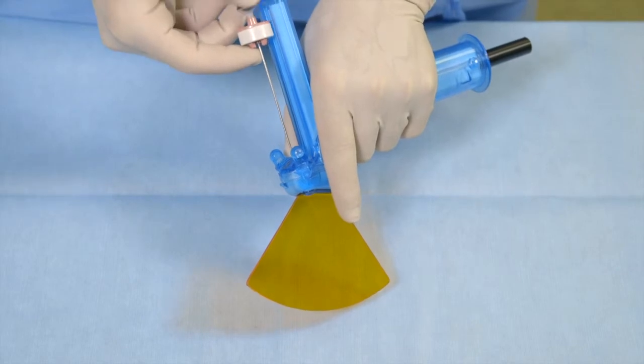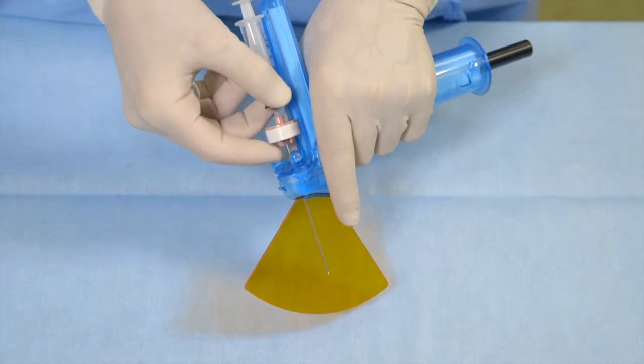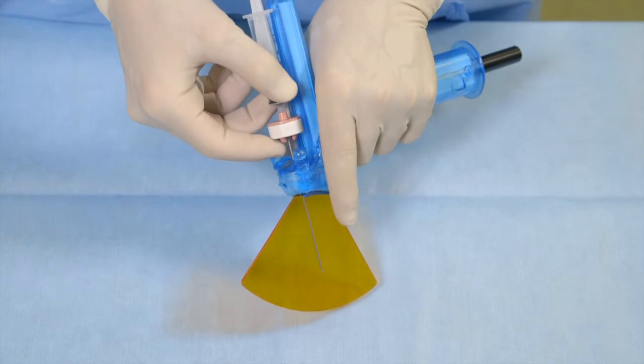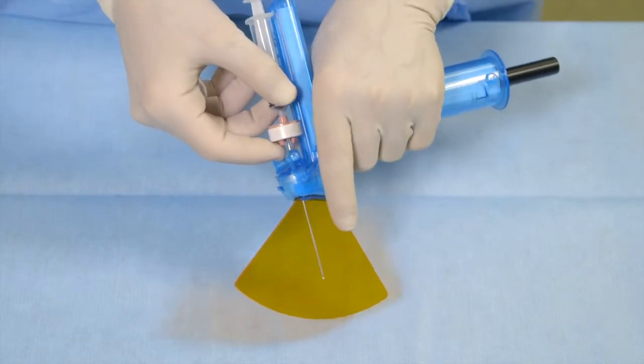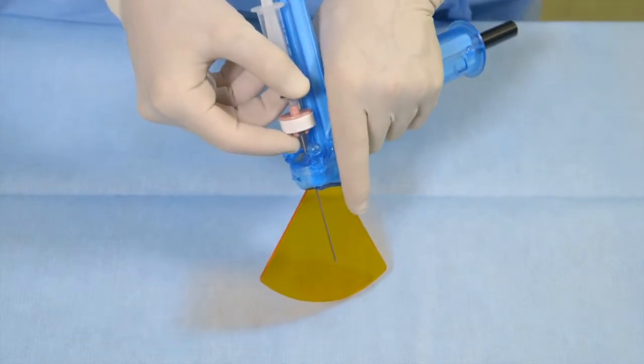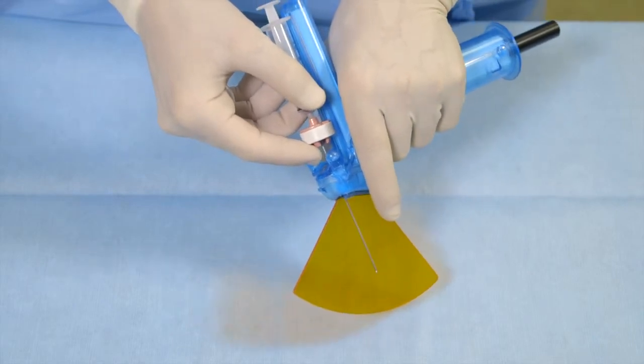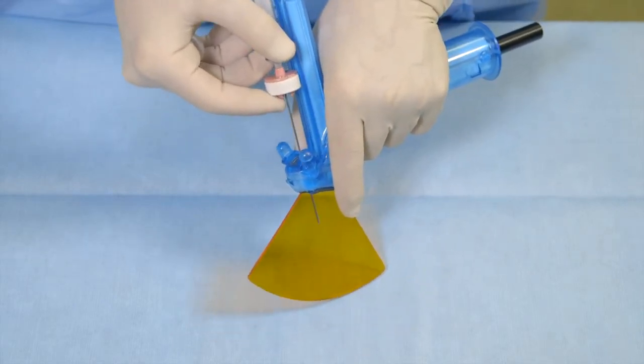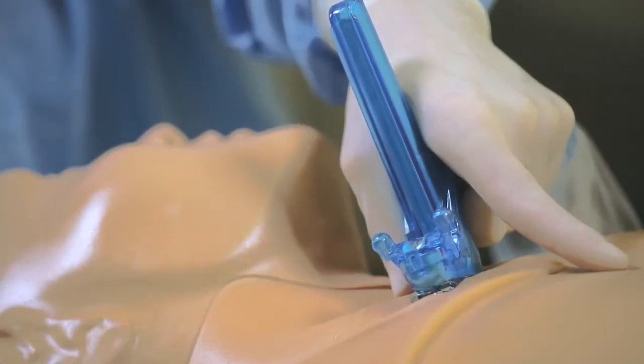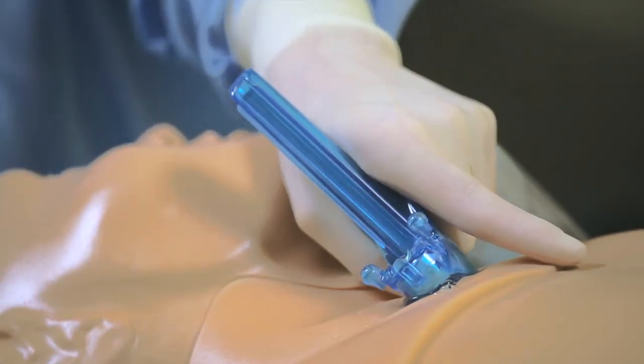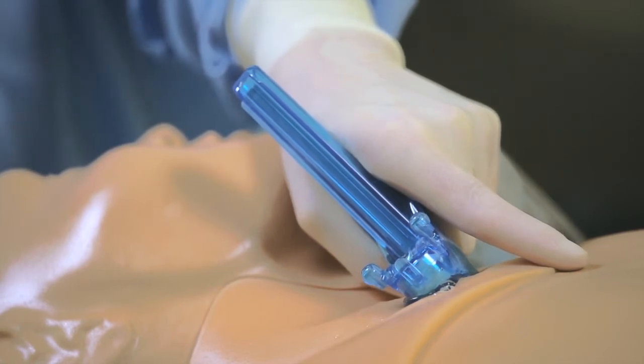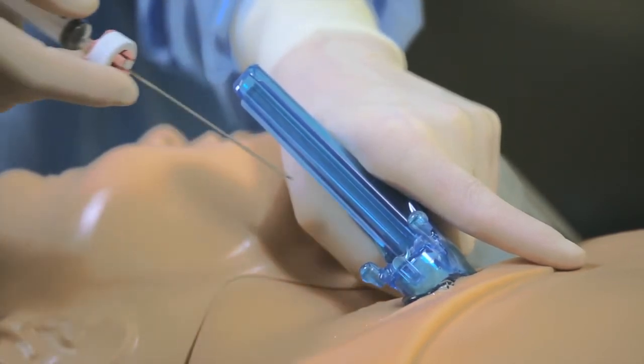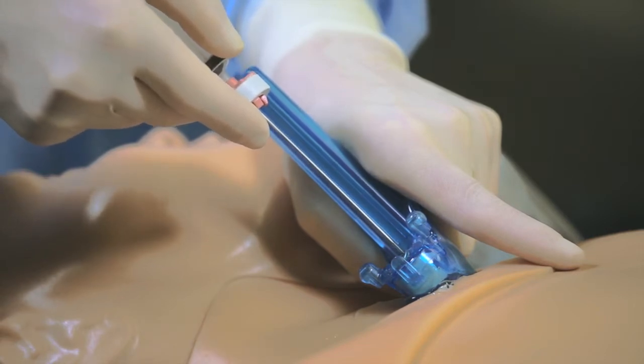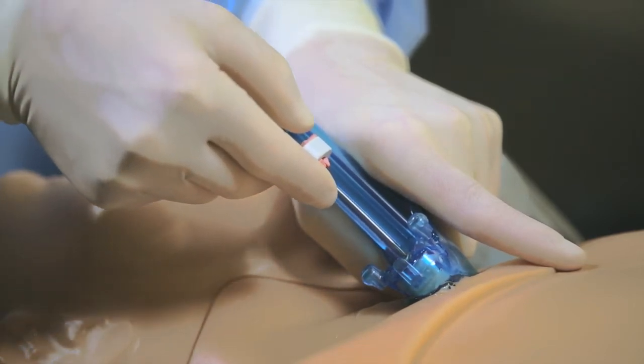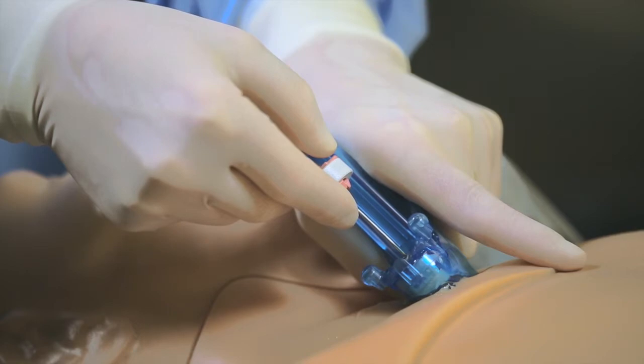Note that the trajectory of the needle is fixed relative to the transducer. In contrast to conventional freehand guidance, the needle trajectory in the AxoTrack system always lies within the scan plane and corresponds to the direction that the transducer is aimed. The transducer does not have to be oriented perpendicular to the body. It can be tipped or angled to find the appropriate window for safe needle penetration, providing tremendous flexibility when performing a variety of needle-guided procedures.